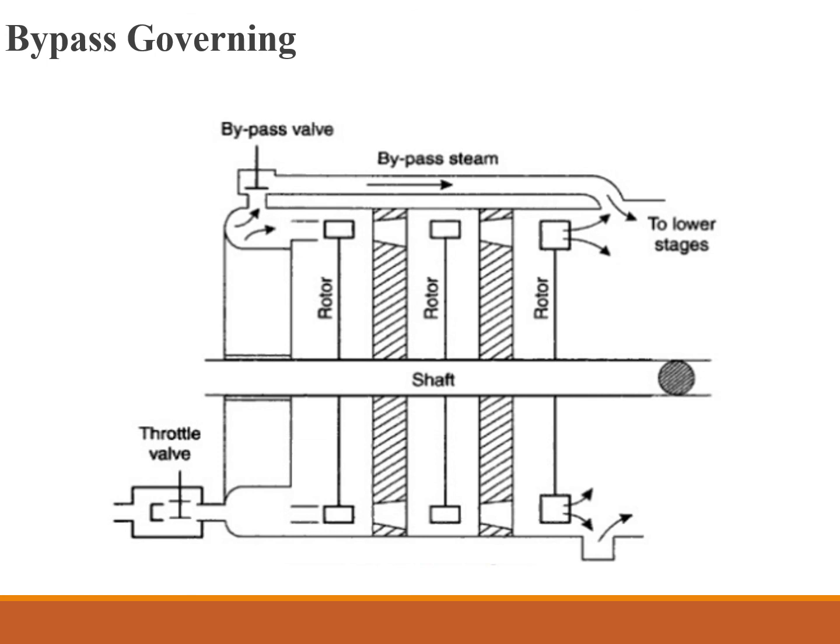A bypass valve opens automatically, allowing the steam to pass from the first stage nozzle box into the steam belt, so the steam enters the nozzle of the fourth stage. As the load on the turbine decreases, the bypass valve closes first. The bypass valve is also under control of the speed governor.